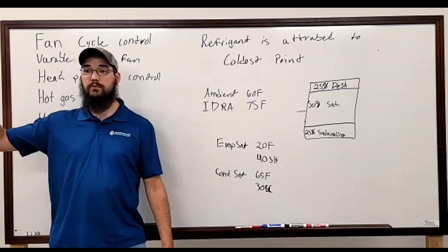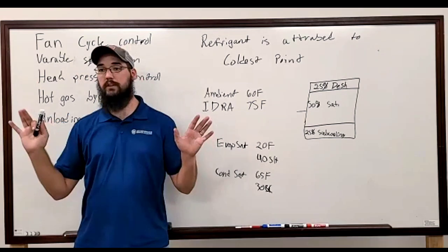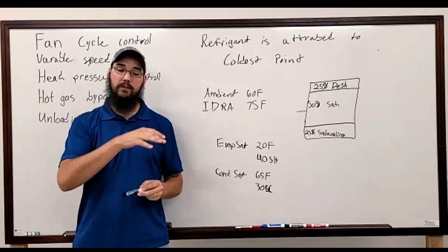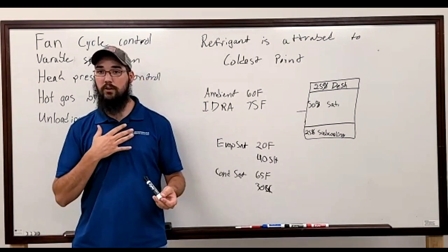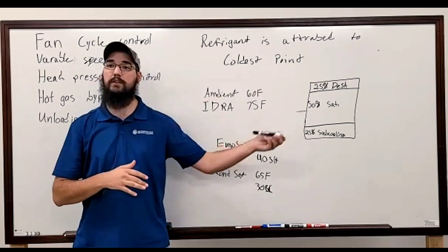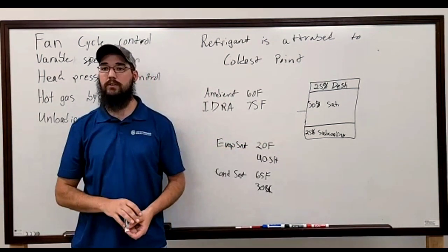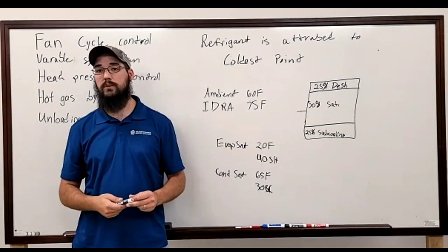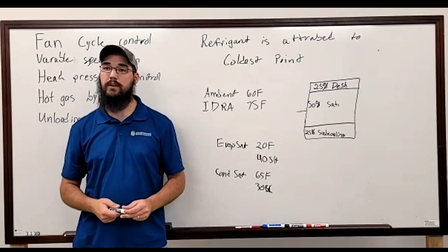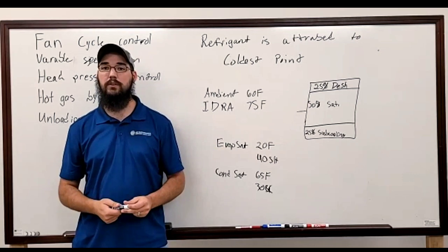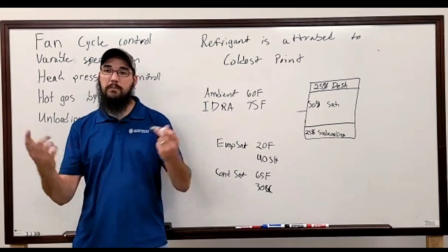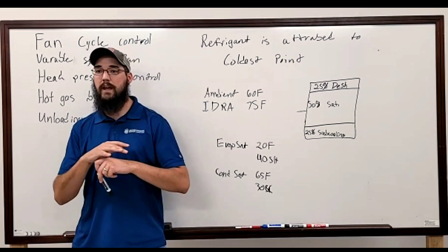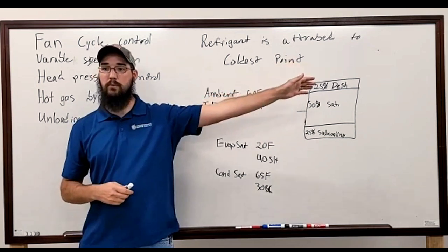He was legitimately concerned that his brand new unit had the fan motor stop working. Now, the space that it was controlling was still completely functioning fine. It wasn't having problems. He just noticed the fan wasn't running. And one of the symptoms, something that he had learned from us and working on other equipment out there, was, well, see if the motor feels hot to the touch. The motor was cold. So he was very concerned, but I explained to him over the phone, what's your outside air temp right now? It was just shy of 60 degrees. I said, okay. The ambient air was cold enough that the fan probably hadn't run since sometime the day before.